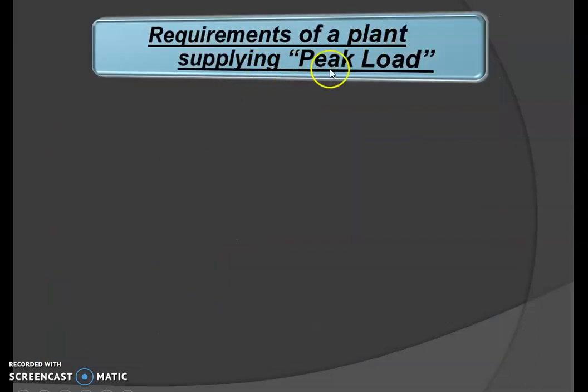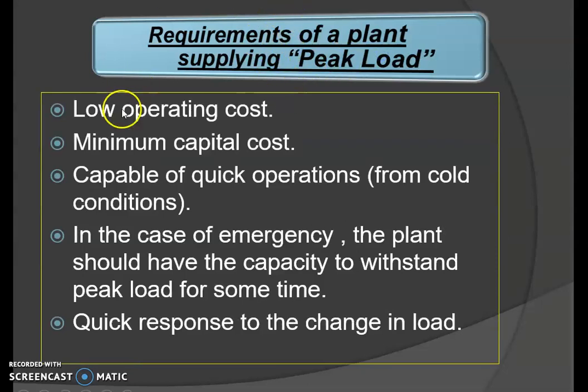Now the requirements of the plant supplying peak load. Peak load plants are only those plants which can be switched on only at the time of the system peak. So the requirements for this are low operating cost, minimum capital cost, and capability of quick operation from cold conditions. These peak load plants include only those plants which can start at once in a quick manner. In the case of emergency, the plant should have the capacity to withstand peak load for some time. Quick response to the change in load. When the load increases, it generally starts quickly.